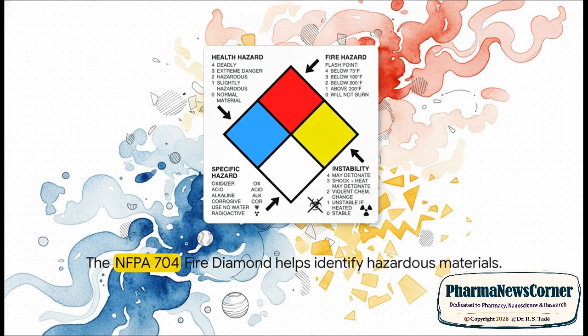And all of this rigorous planning translates directly into visual cues in your environment. Take a look at the NFPA 704 standard, widely known as the fire diamond. You've definitely seen this on the doors of chemistry labs or on industrial tanks around campus. Emergency personnel use this to instantly identify hazards on a scale from 0 to 4. The blue diamond is the health hazard, red is flashpoint and fire hazard, yellow is instability, and white denotes specific hazards like corrosive or radioactive materials. It's an immediate, universal language of risk.